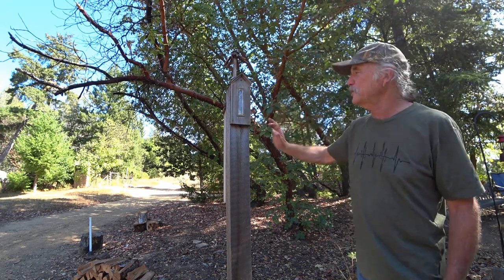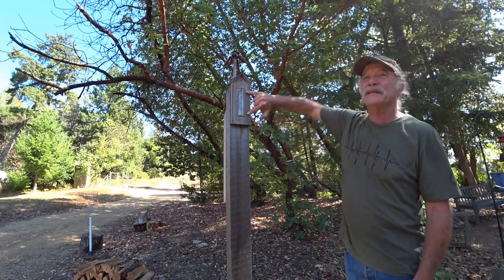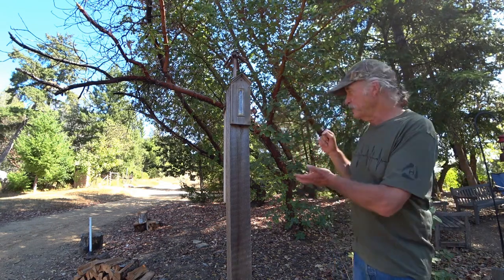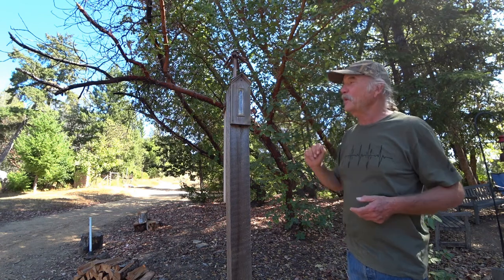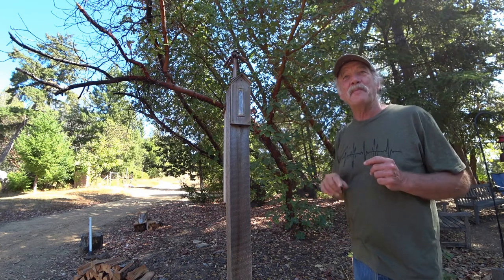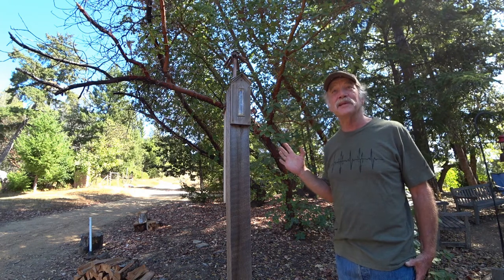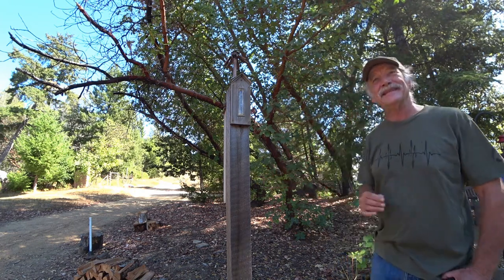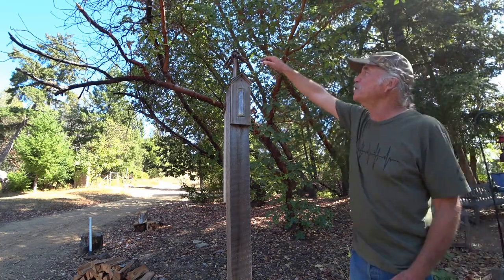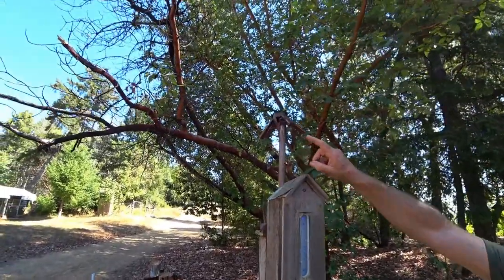And on the downhill line from the tanks, there's 10 more water pressure switches that each correspond to a different level of the pressure that would be present at those levels in the tank. So when I look at this gauge, I know how much water is in my tanks. They're full right now. Every time that blinks, I know that my pump is running and how fast it is running. So at a glance, I know the entire status of the water system from something that sits right here, with a 1 foot by 1 foot footprint. It's beautiful. And what powers it is these little solar panels up here. I call this a static tracker.